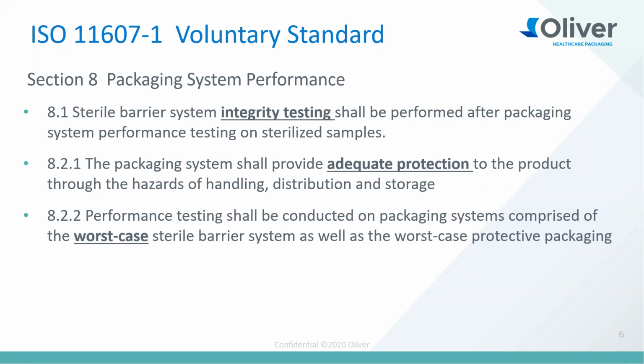So there are some key highlights we've taken from section 8 of this 11607 standard. The first one I've just mentioned is the integrity testing. Following the schedule, you will execute bubble leak or dye penetration testing to ensure that the primary package that you've selected meets your specific requirements. It's also important to note that when you're doing your packaging simulation testing, performance testing, you have adequate protection to the product through the hazards, in order to ensure that during the hazards it has the best opportunity to pass. And then finally, when you're doing your performance testing, you need to consider working on the worst case scenario. So the worst case sterile barrier system and worst case packaging.